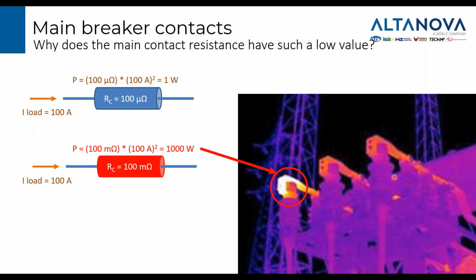Important that the value of the resistance remains well below a few microohms. I try to explain with numbers. If we have a load current of 100 amps, which is, let's say, a reasonable value for a load current, that flows into 100 microohms as a contact resistance, we see that the power dissipated is 1 watt.